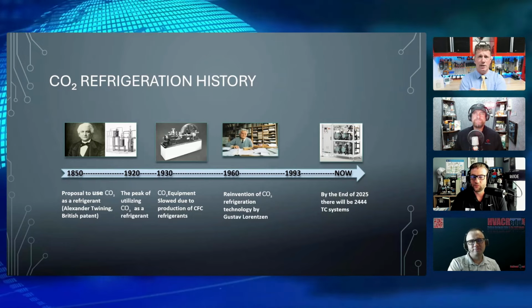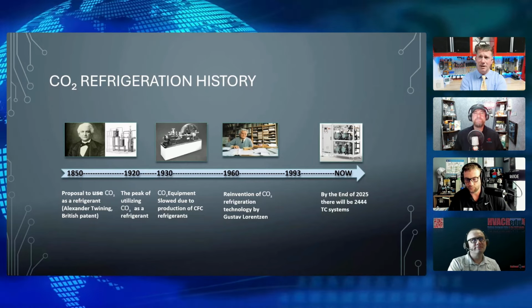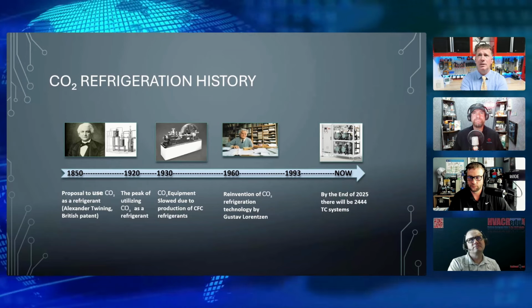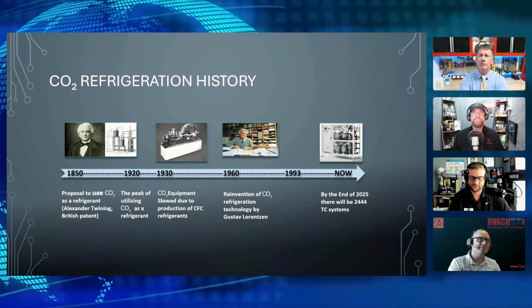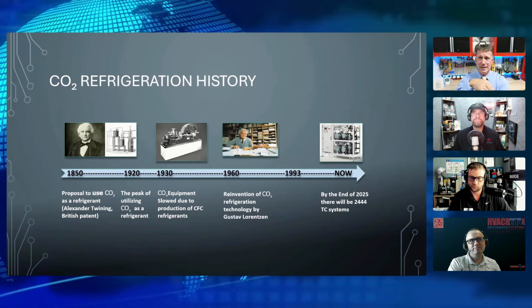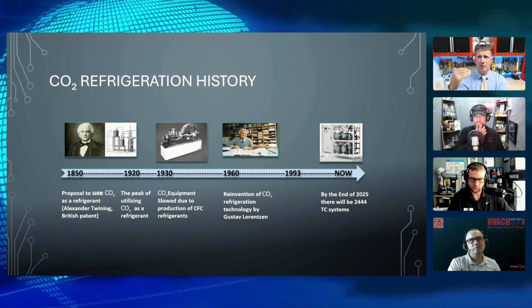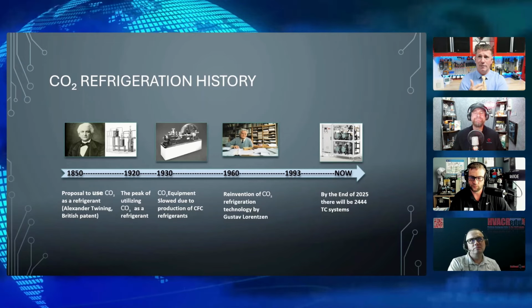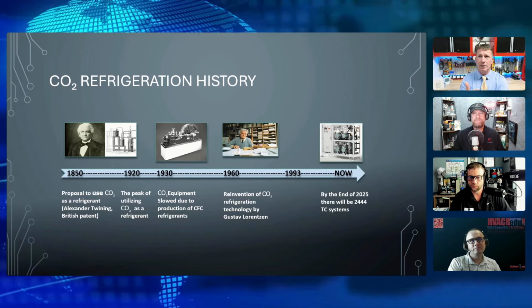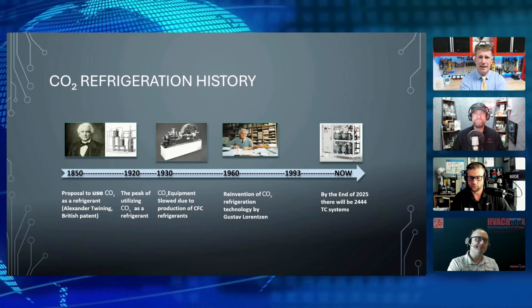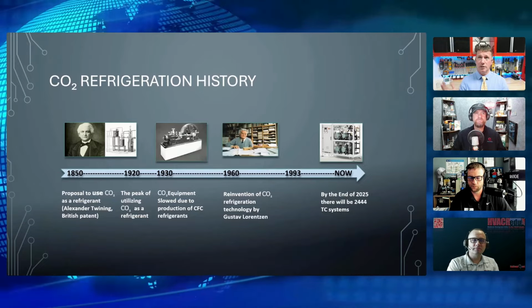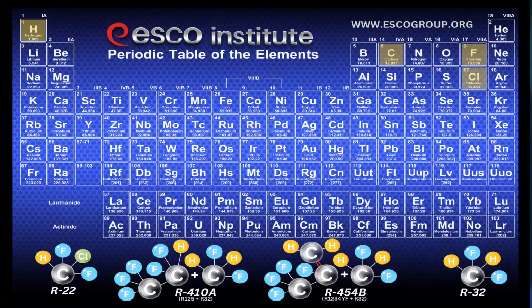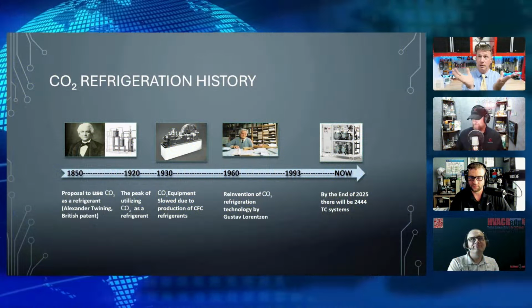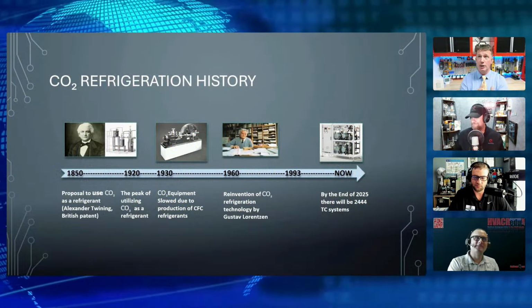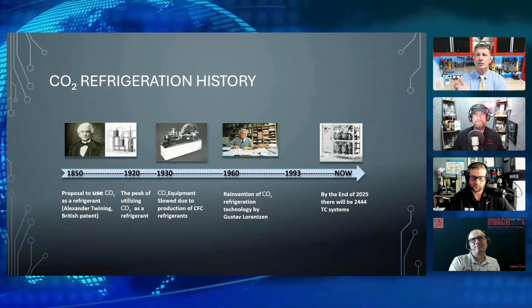Absolutely. A lot of people don't realize where we are with the HFC phase down. We're currently at 700 GWP in a lot of applications, and 150 GWP in many other applications, including automotive and some of our refrigeration. As we continue down this scale and start reducing those GWP limits, we're going to have to rely on more natural refrigerants like CO2, R290, ammonia, R600, 600A. Our low GWP counterparts are going to be the solutions going forward, because our chemists will tell us we don't have anything else. We just put out the refrigeration chemistry chart, and you're looking at the actual periodic table. Dr. Chuck reached out and said, we're grateful you're doing this, because people don't realize the periodic chart is not growing. But people are expecting us to make more and new things, and we can't do very much with what we have. So we're going to see a lot of CO2.